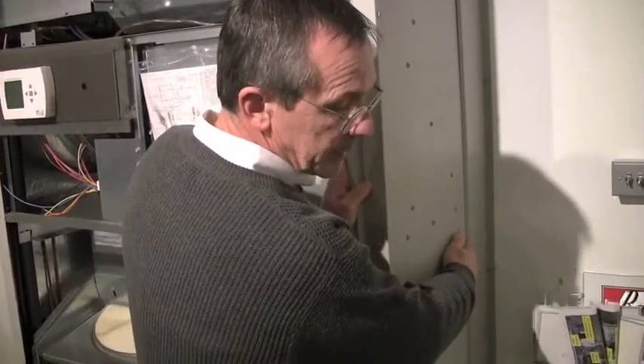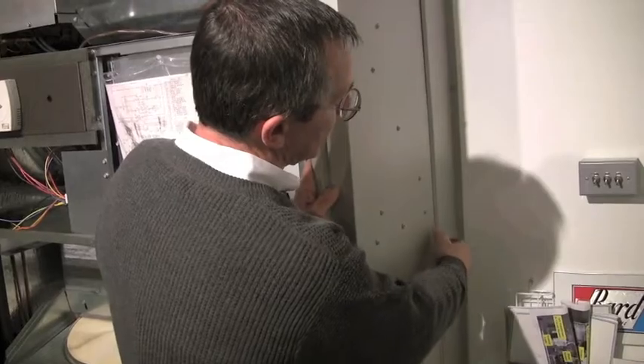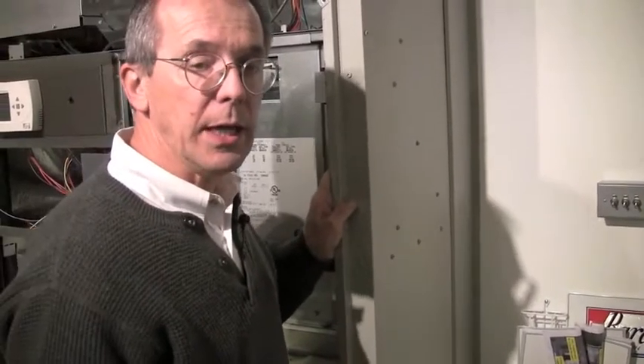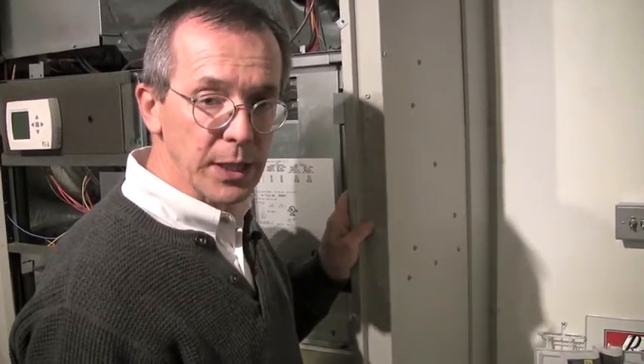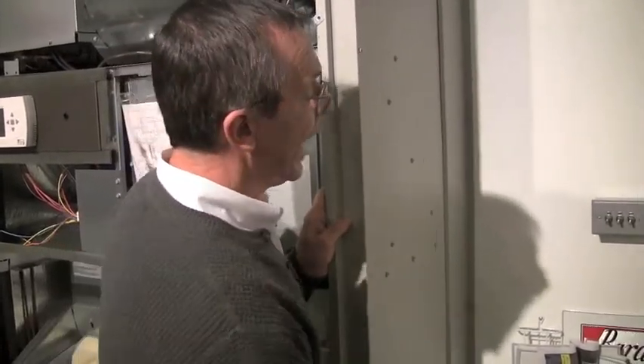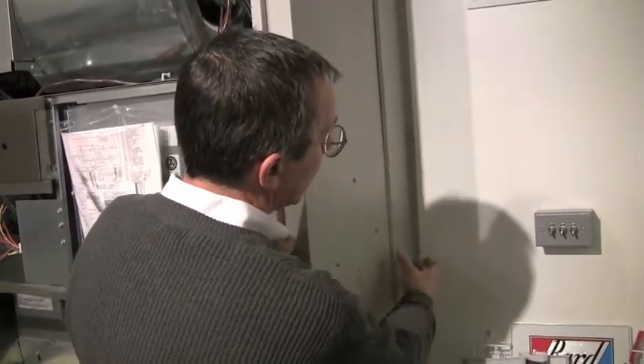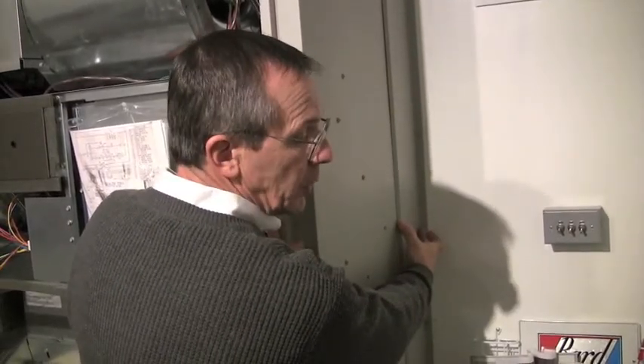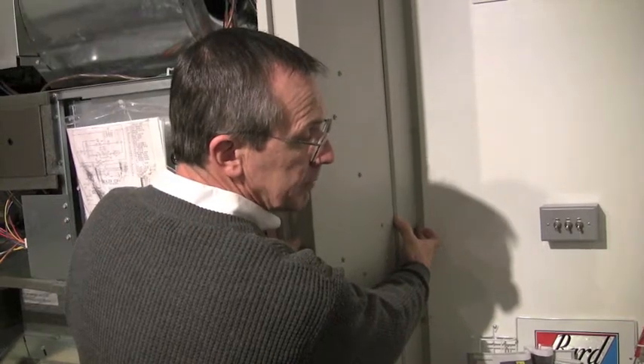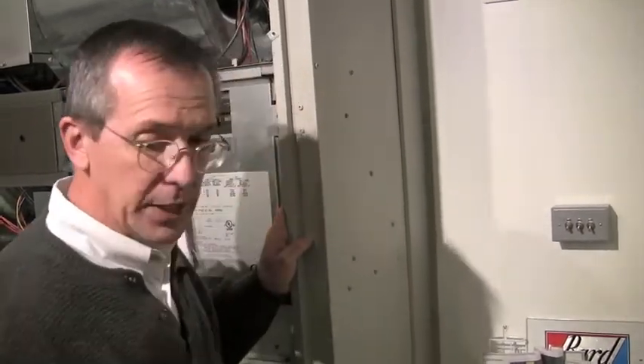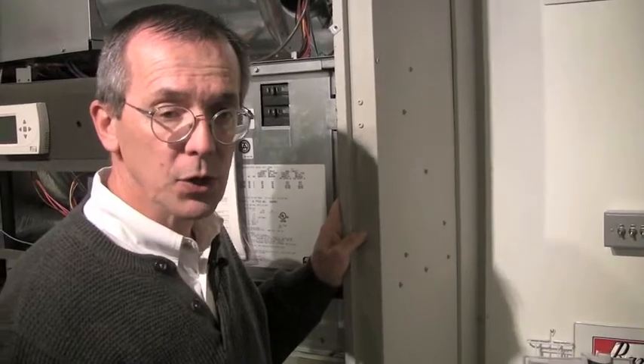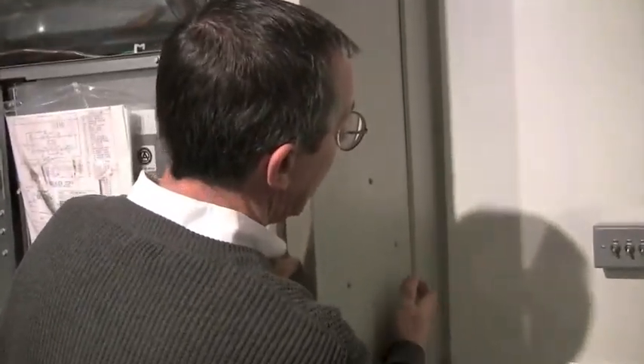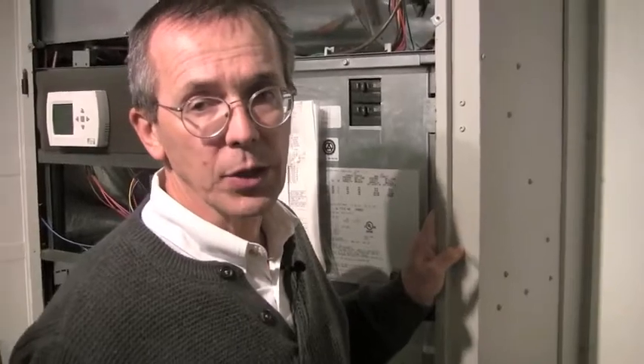bottom of the unit. For aesthetic purposes, Bard has given us a trim kit to cover the distance between the back of the unit and the wall, remembering that the wall sleeve, the standard wall sleeve, is 14 inches thick. So if we have a wall that is 12 inches thick, there's going to be a 2-inch gap between the unit and the wall. So if we have a 10-inch wall, there's going to be a 4-inch gap.